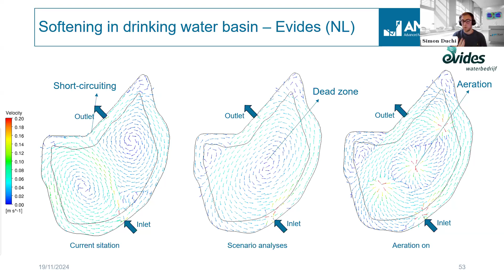Of course, only from velocity vectors, it's a bit difficult to really conclude something. So we also typically run the mean water age, which gives you an idea of how old the water is at each location in your basin. For example, you can clearly see the short circuiting at the younger water that flows just from the inlet and part flows to the outlets. In our new simulation with the scenario, we had this big dead zone in the middle. And when the aeration is on, we have a very uniform mean age in the basin. Only at the side you can see the incoming flow still visible.